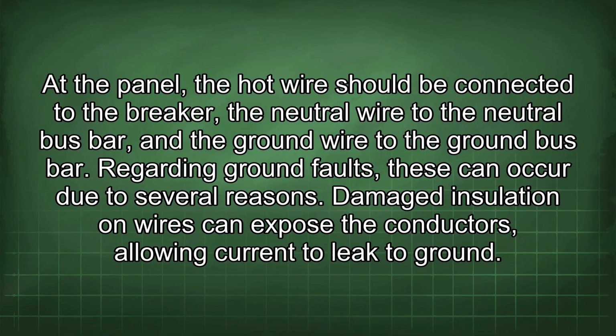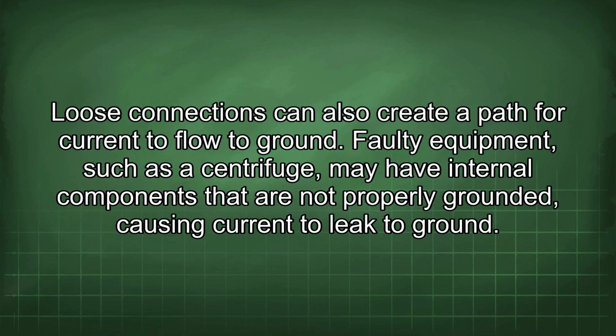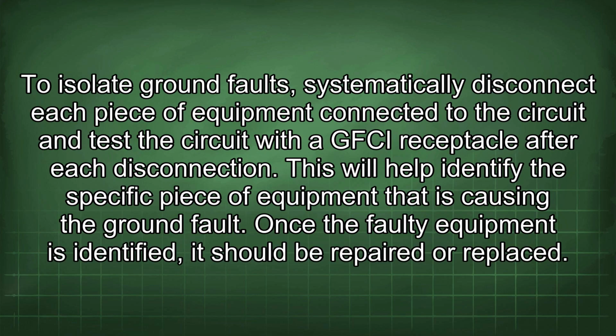Regarding ground faults, these can occur due to several reasons. Damaged insulation on wires can expose the conductors, allowing current to leak to ground. Loose connections can also create a path for current to flow to ground. Faulty equipment, such as a centrifuge, may have internal components that are not properly grounded, causing current to leak to ground. To isolate ground faults, systematically disconnect each piece of equipment connected to the circuit and test the circuit with the GFCI receptacle after each disconnection. This will help identify the specific piece of equipment that is causing the ground fault. Once the faulty equipment is identified, it should be repaired or replaced.